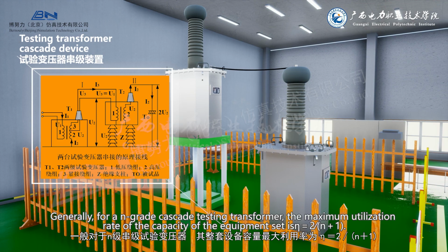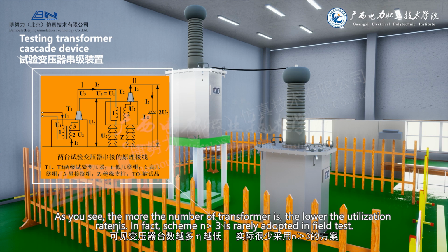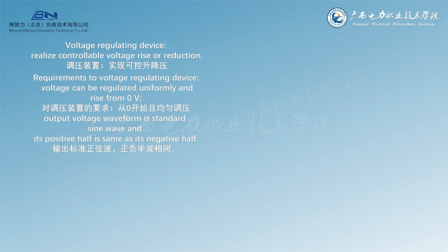Generally, for an N-grade cascade testing transformer, the maximum utilization rate of the capacity of the equipment set is 2/(N+1). As you see, the more transformers there are, the lower the utilization ratio. In fact, schemes with N greater than 3 are rarely adopted in field tests. Voltage regulating device: realize controllable voltage rise or reduction.